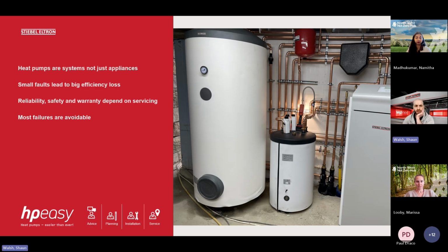So if we take a look at a typical heat pump system, I hope you can all see my screen okay. We'll just have a quick look at this. A heat pump system is not just an appliance. Here you can see we've got a domestic hot water tank, buffer cylinder, expansion vessel, and there's a lot of pipe work and things like that. All of these things have to work together to make the heat pump run effectively.